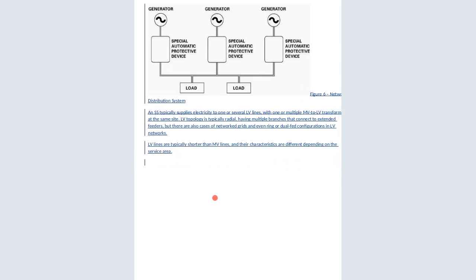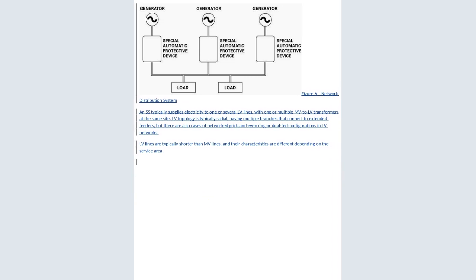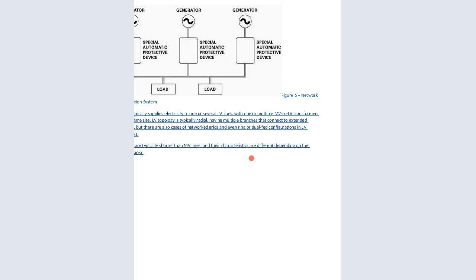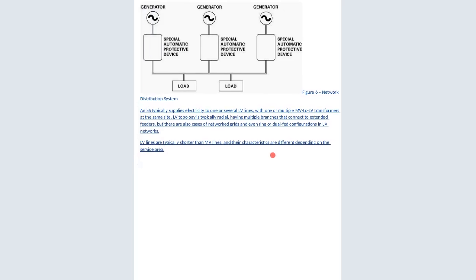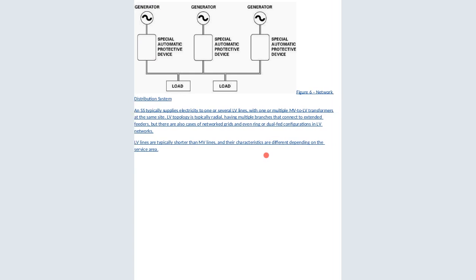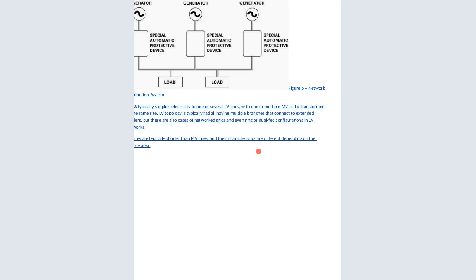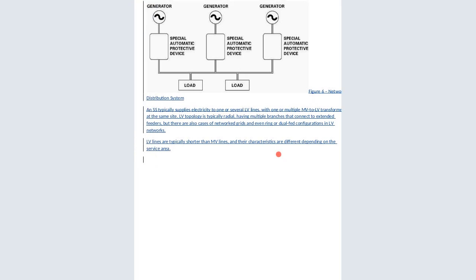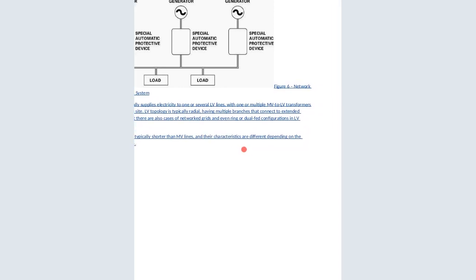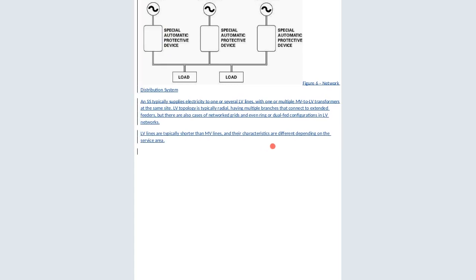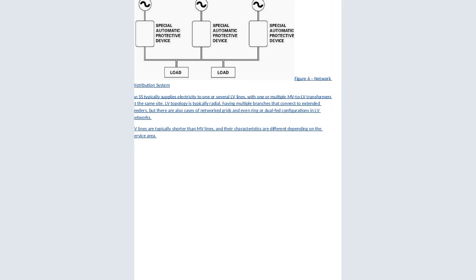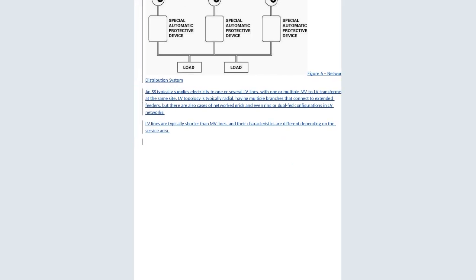This is a secondary substation, which typically supplies electricity to one or several lines, with one or multiple MV/LV transformers at the same site. The LV topology is typically radial, having multiple branches that connect to extended feeders. But there are also cases of networked grids and even ring and/or dual-fed configurations in LV networks. The LV lines are typically shorter than MV lines. I said LV means low voltage, and their characteristics differ depending on their service area. So those are the supply systems that we have.